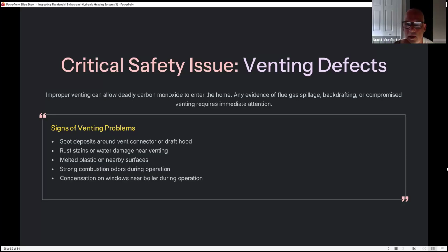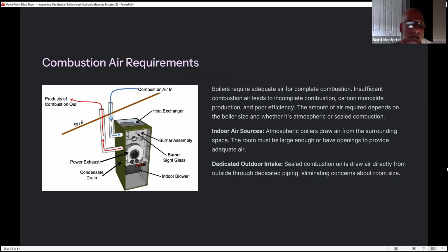Yes. I always do. As Jim said before, they should have a metal liner. A lot of times when they go from oil to gas, they should line it, and they don't, or at least have that liner. Most of the liners are spalling, they're broken, et cetera. So you'll see it on top. If you go up on the roof, you'll see if there's a liner. If you can't see it and you're not sure, like Jim, I have a disclaimer that says I have somebody clean, inspect, and verify that the chimney is properly lined. So I do mention it. There's nothing wrong with mentioning it. Just cover yourself.